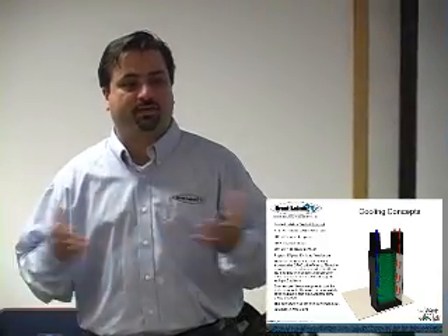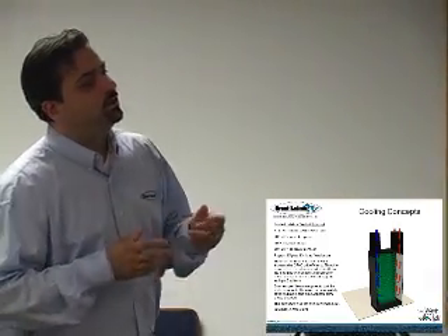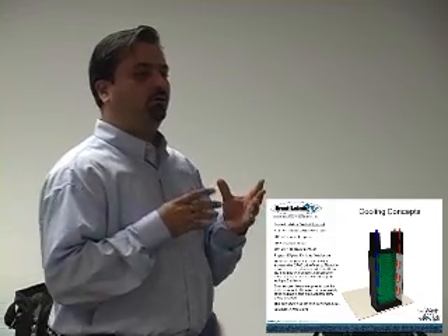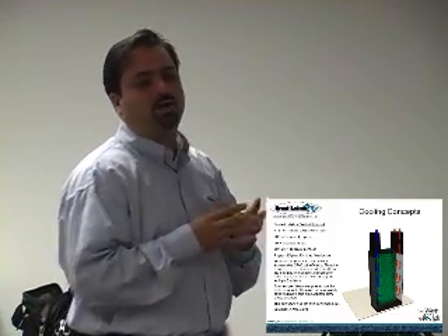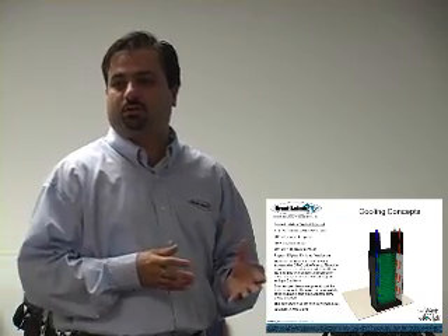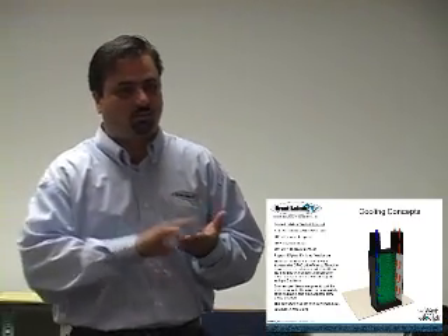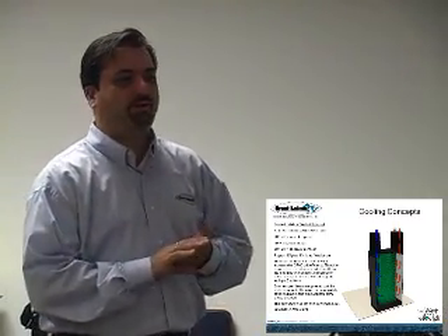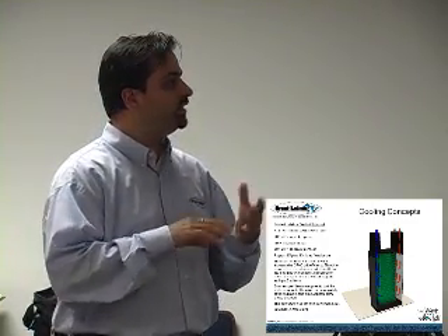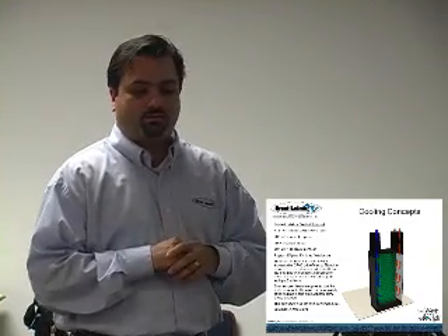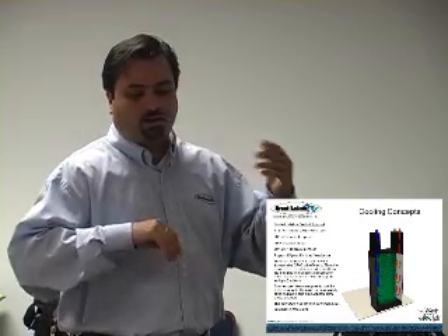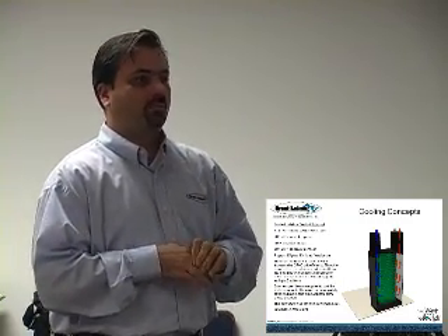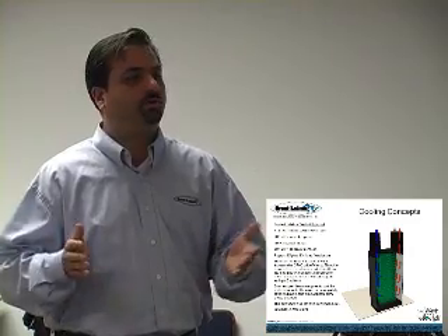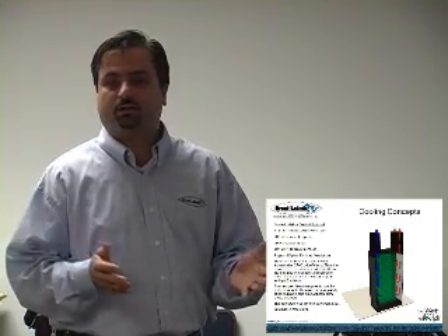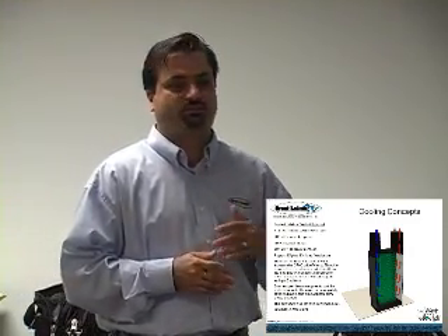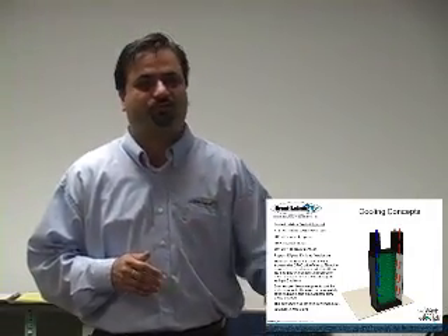The concept we're trying to promote is basically to stay passive. We really don't want to add anything, everyone has enough redundancy built into your CRAC unit. You have the power, the PSUs, and the backup generators running all your power to the servers. So we don't want to add another AC system or another fan-assisted system. You already have enough cooling into your CRAC units typically, usually over 2 to 3 times what your actual heat load is.